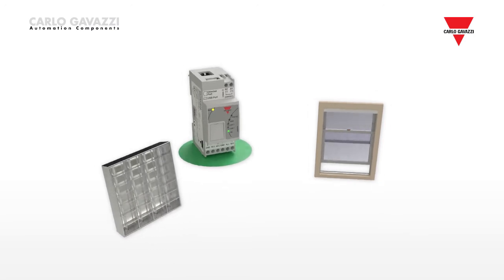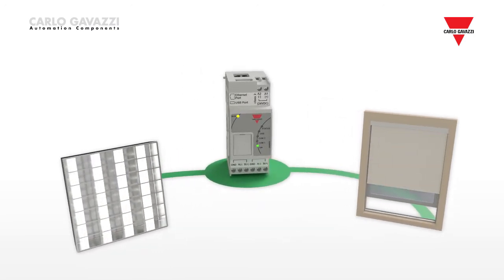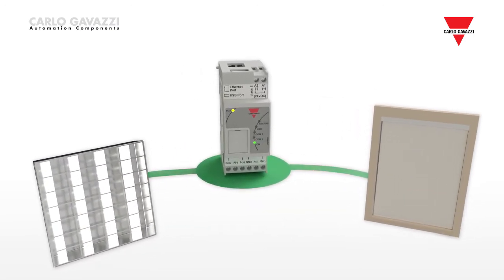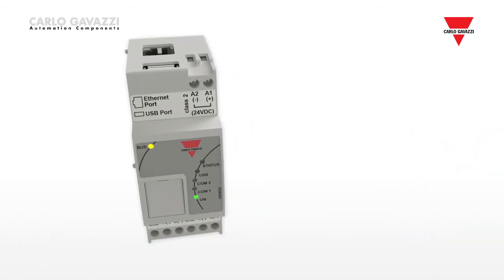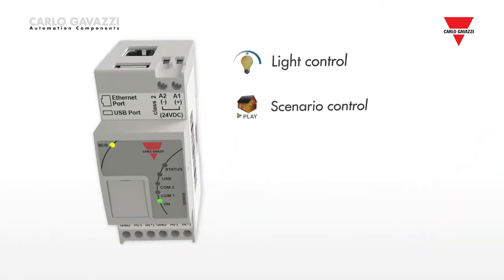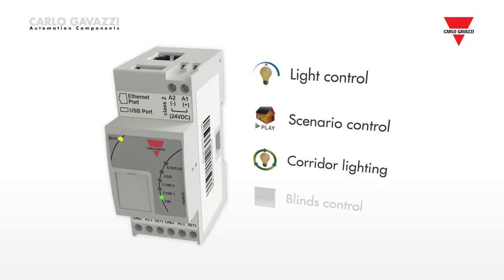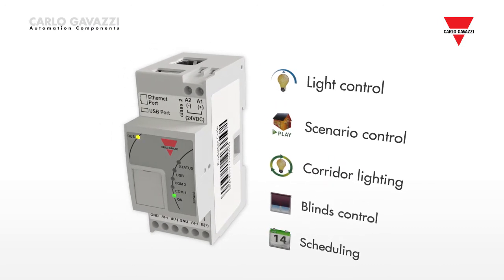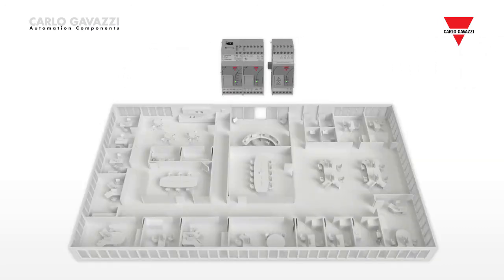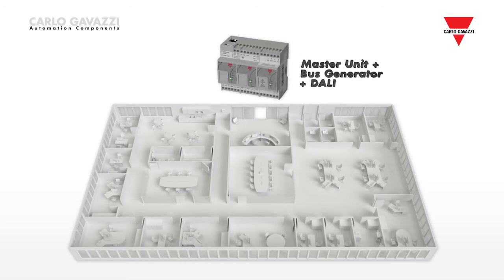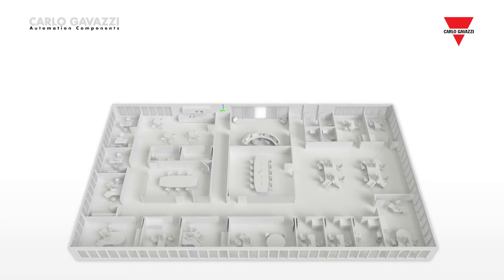For lighting and blinds control, the SB Web BACnet controller runs the strategy. This includes functions such as constant light control, scenario control, corridor lighting, blinds control, and scheduling. The interface to the dimmable lighting loads is implemented through the DALI bus, the standard for lighting actuators.